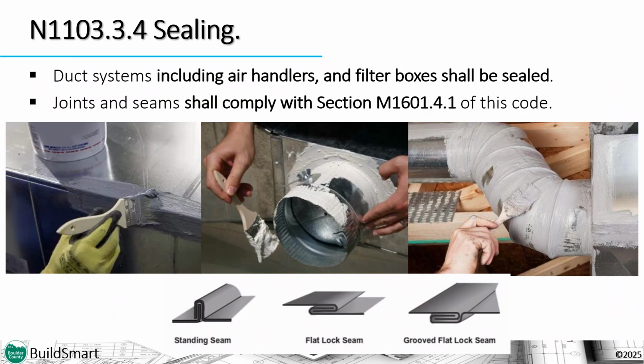The reality is that all joints, seams, boots, connections, and all holes in a duct system are required to be sealed. All ductwork, including ventilation, dryer, and kitchen hood duct, is required to be sealed per the IRC. Liberally applied mastic is your best tool to use to make the duct airtight. Flex duct primarily leaks at the connection points, and there are several resources for best practices for installing flex duct that should be considered that go beyond the air sealing.